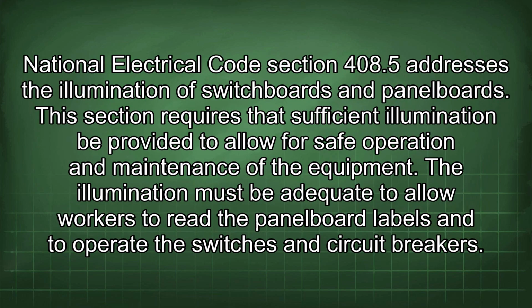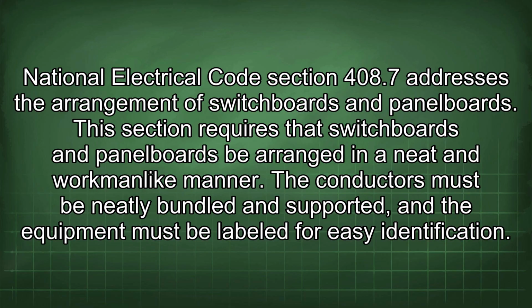National Electrical Code Section 408.5 addresses the illumination of switchboards and panel boards. This section requires that sufficient illumination be provided to allow for safe operation and maintenance of the equipment. The illumination must be adequate to allow workers to read the panel board labels and to operate the switches and circuit breakers. National Electrical Code Section 408.7 addresses the arrangement of switchboards and panel boards.